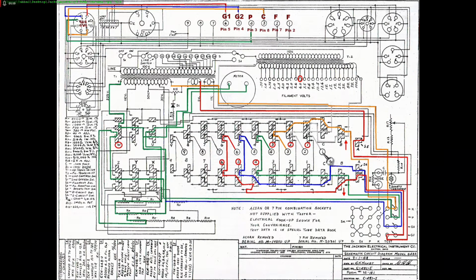So if we go to 1 here, 1 corresponds to pin 2 filament. If we follow that, when this is depressed, the segments slide up and we see the connection that it makes, and it goes to the common, minus, ground, whatever you want to call that connection on the transformers. So one side of the filament is connected to common through this switch.